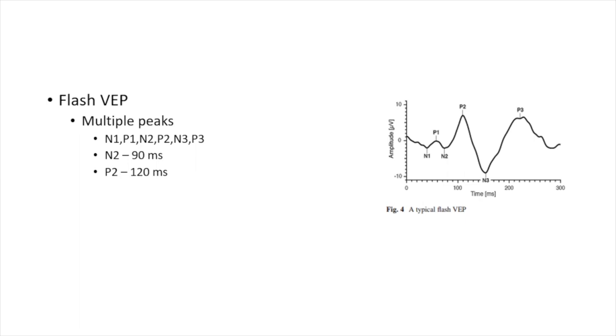Flash VEP has about six waves — three negative (N1, N2, N3) and three positive (P1, P2, P3). The most important are N2 and P2: N2 comes around 90ms and P2 around 120ms after stimulus onset. At least a minimum of two recordings should be done to confirm reproducibility. All electrophysiological tests — VEP, ERG, extended protocols, MFERG — require laboratory-specific normative data. A VEP from a different lab cannot be compared to one from your own lab.